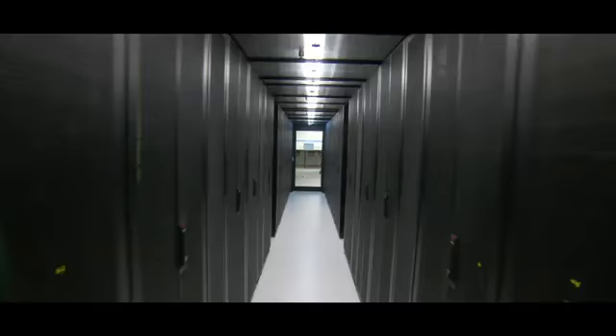When we installed the Schneider Electric cooling system for Pod 1, together with the hot aisle containment system, we saw that high density was possible, and we decided to take it to the next stage when we implemented Pod 2. With the Schneider Electric solution, it is possible to run it over 20 kilowatt per rack and keep the system stable. We're also saving money here.